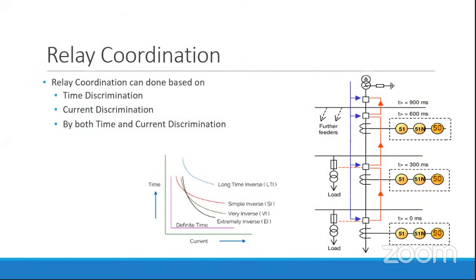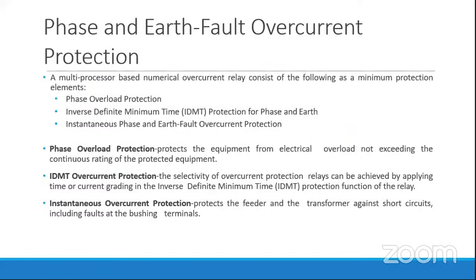So as I said, protection relay coordination is normally done from time and current discrimination, and the coordination is for the current based protection. Normally there are two types of protections: phase fault and earth fault protections. The protections should be given in a certain manner, that is, overload protection, inverse definite time protection, and instantaneous phase and earth fault protection.